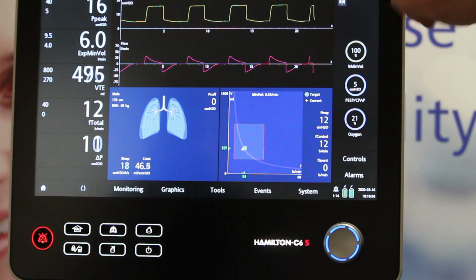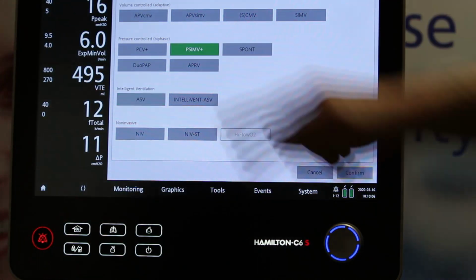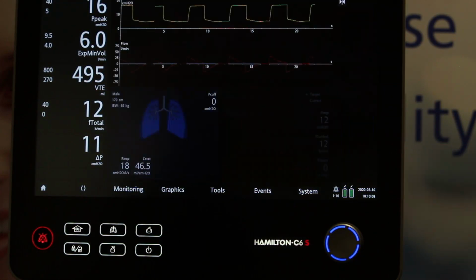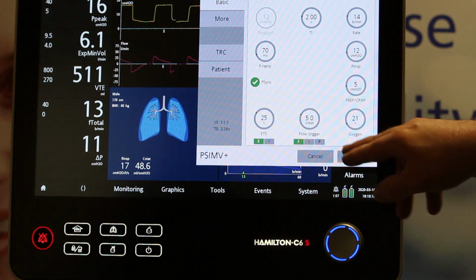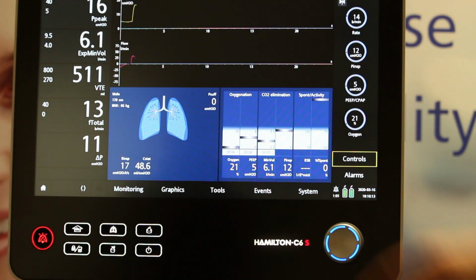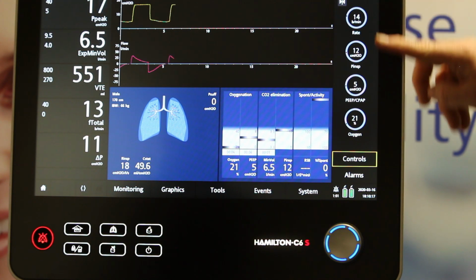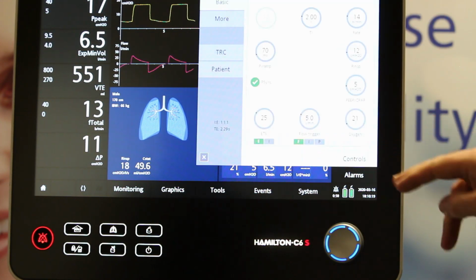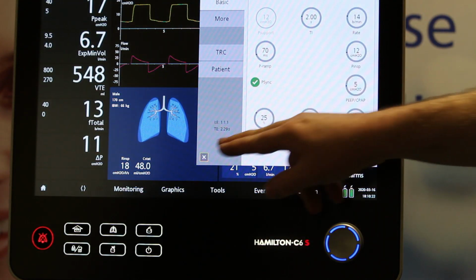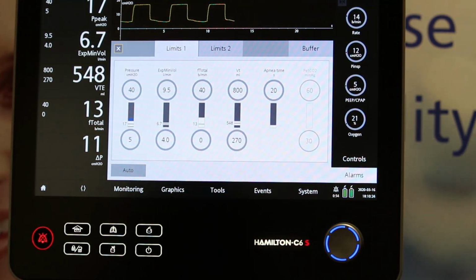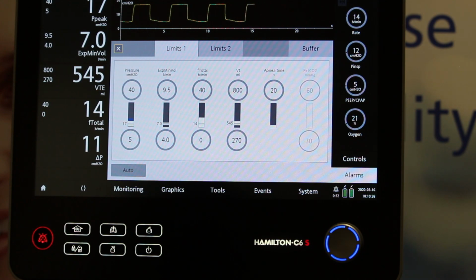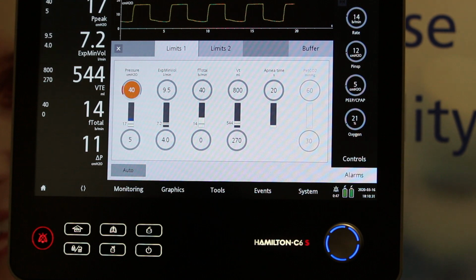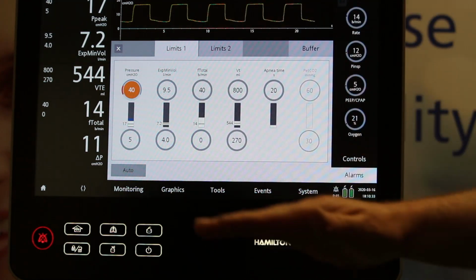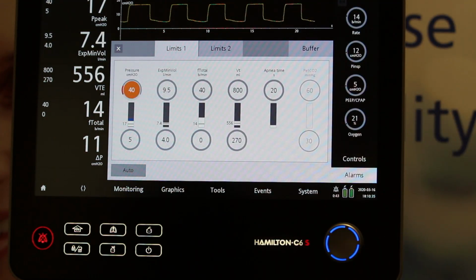If you want to change into any other mode, just press your mode button. We pick pressure SIMV, confirm. If we're happy with those controls, confirm, and you see the ventilator has just slipped in to the mode that we've picked. So we've got our main controls over here on the right hand side. The controls brings me back into that control screen. Alarms then is where I can manually adjust any of the alarms. There's a Pmax alarm here. All Hamilton modes default to a Pmax of 40. There's a restriction 10 centimetres of water below what your Pmax is set at.